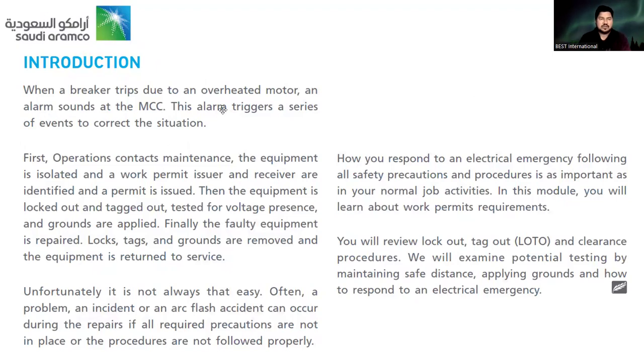Just a scenario: a breaker trips due to an overheated motor, and an alarm sounds at the MCC. This alarm triggers a series of events to correct the situation. First, operations contacts maintenance. The equipment is isolated, a work permit issuer and receiver are identified, and a permit is issued. Then the equipment is locked and tagged out, tested for voltage presence, and grounds are applied. Finally, the faulty equipment is repaired. Locks, tags, and grounds are removed, and equipment is returned to service.